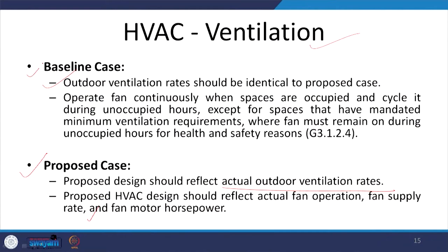So, it should be reflecting the actual outdoor ventilation rate both in the proposed and baseline case. However, the operation schedules may vary for the proposed case, where on the basis of temperatures or occupancies, the HVAC supply of air will be reduced or cut off if certain conditions are prevailing. So, the schedules of operations which are programmed, which are specialized, may be used in the proposed case but not in the baseline case.